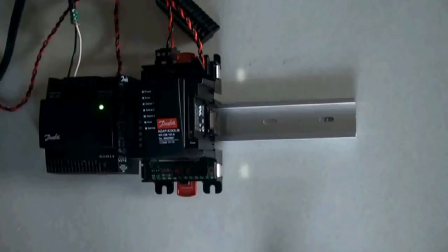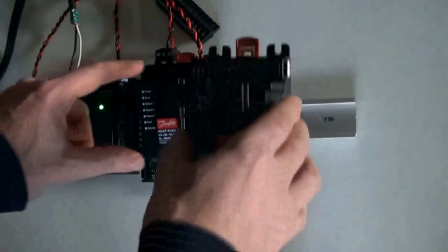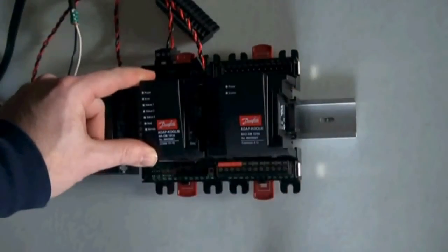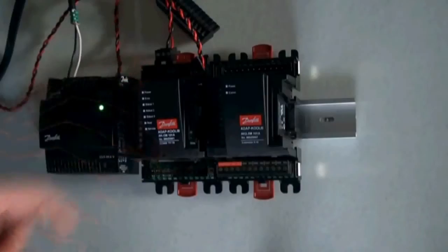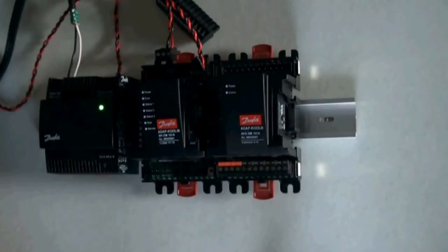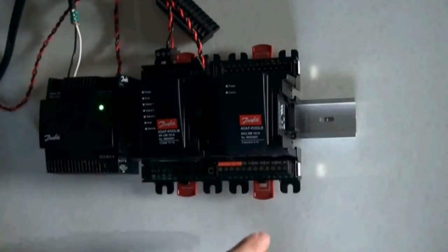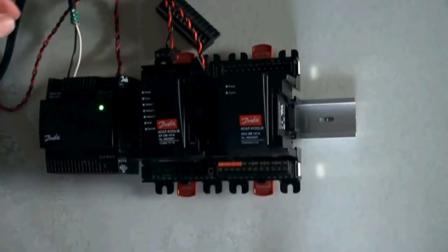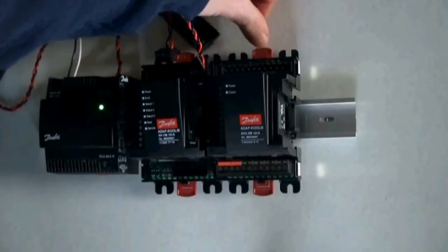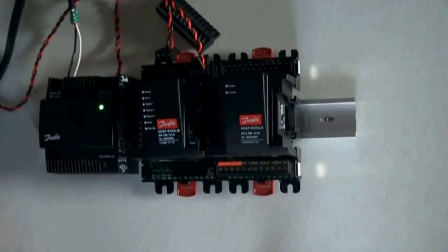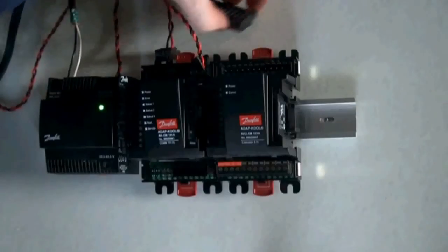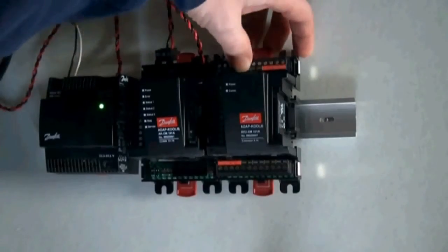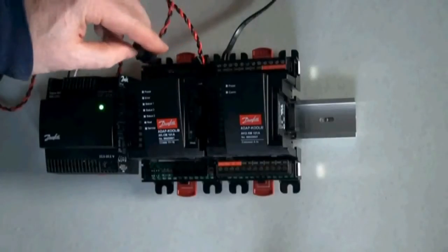To reinsert a module, first line up the Z connector, then push the module into place. It's important that it's lined up with other modules on the group. To lock the module to the DIN rail, press the red tab at the bottom and the top. The last step is to reconnect any terminal strips and reapply power.